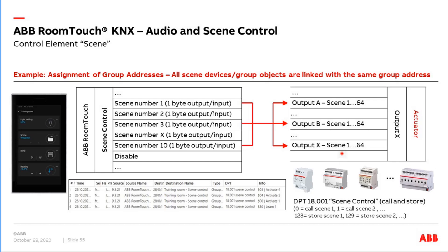In the group monitor you can see: I press a button and send 'Activate scene number 4', meaning call scene 4. Then activate number 5, number 1 — calling different scenes, but it's only one telegram and one group address. Depending on the value, different scenes are called. The last telegram shows I pressed long and sent the command 'Learn scene number 1' — store. Then all devices linked with the group address know they must now store their current value. The next time scene number 1 is called, they will recreate that same situation.